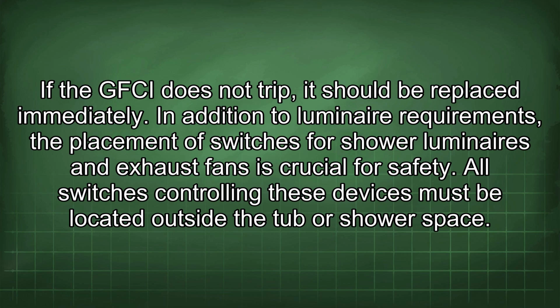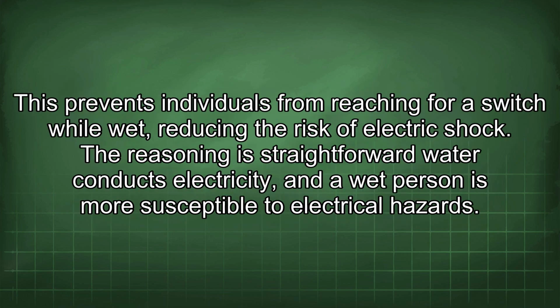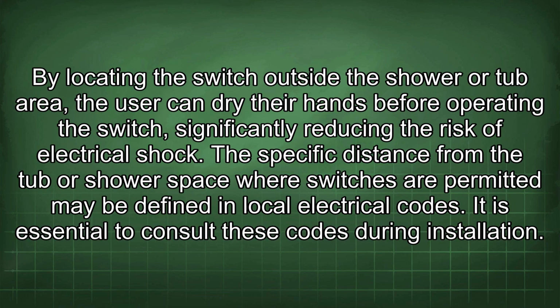In addition to luminaire requirements, the placement of switches for shower luminaires and exhaust fans is crucial for safety. All switches controlling these devices must be located outside the tub or shower space. This prevents individuals from reaching for a switch while wet, reducing the risk of electric shock. The reasoning is straightforward: water conducts electricity, and a wet person is more susceptible to electrical hazard. By locating the switch outside the shower or tub area, the user can dry their hands before operating the switch, significantly reducing the risk of electrical shock. The specific distance from the tub or shower space where switches are permitted may be defined in local electrical codes. It is essential to consult these codes during installation.